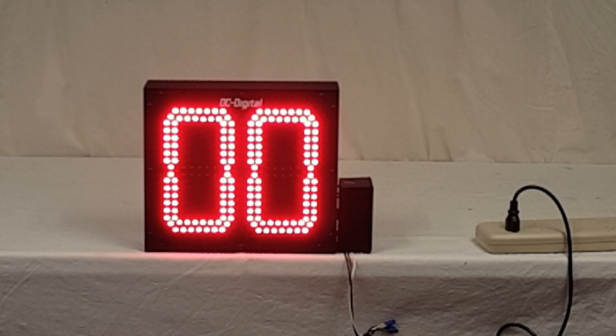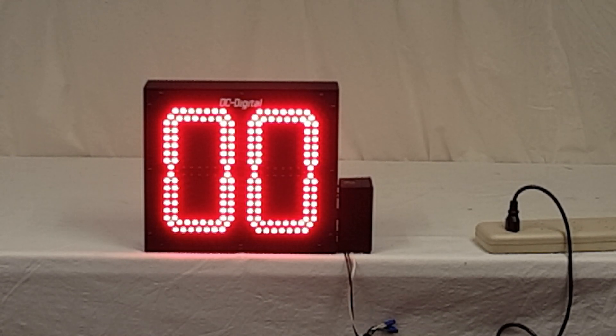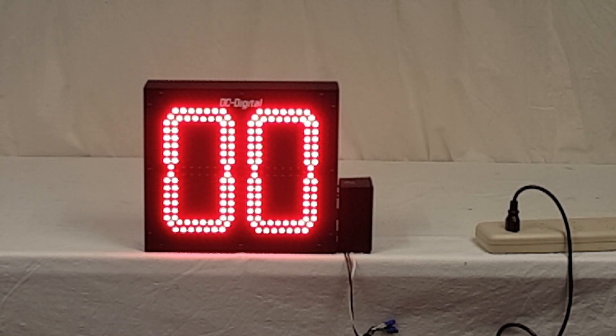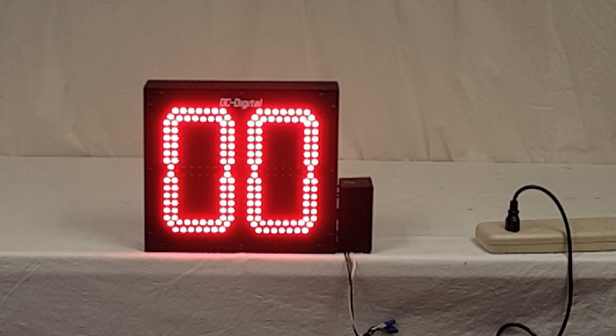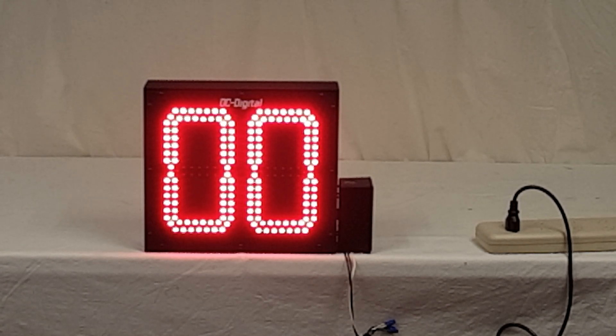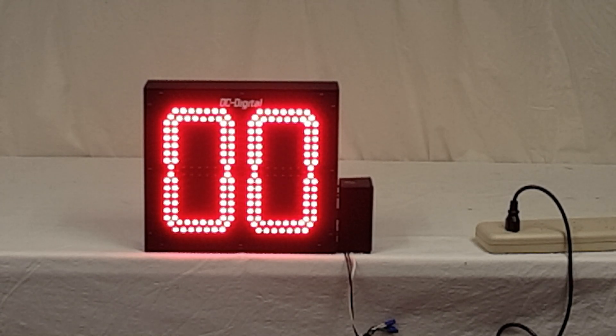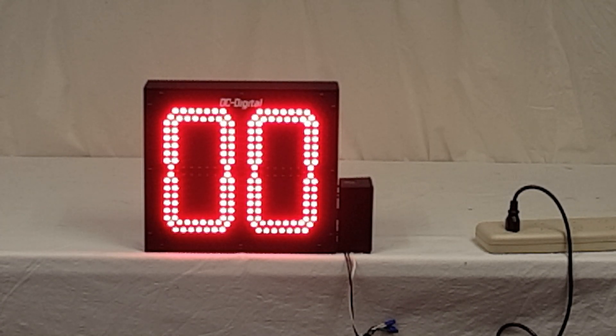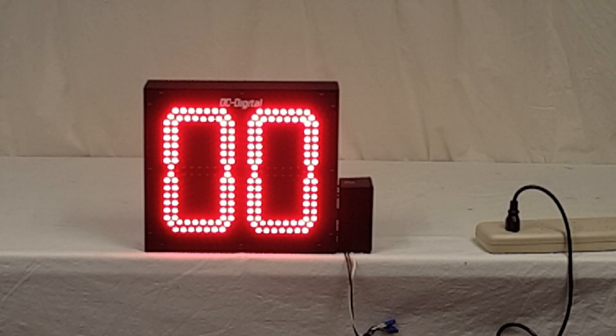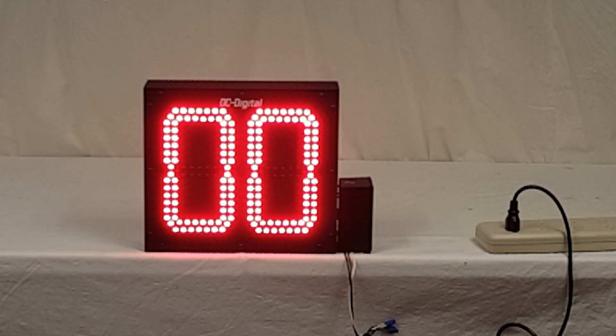The only input on this is that when they apply 120 volts to it, it will go to the preset value set on the rotary switches mounted on the bottom, and I'll show you that in a minute on how to set those. It'll go to that value and immediately start counting down.